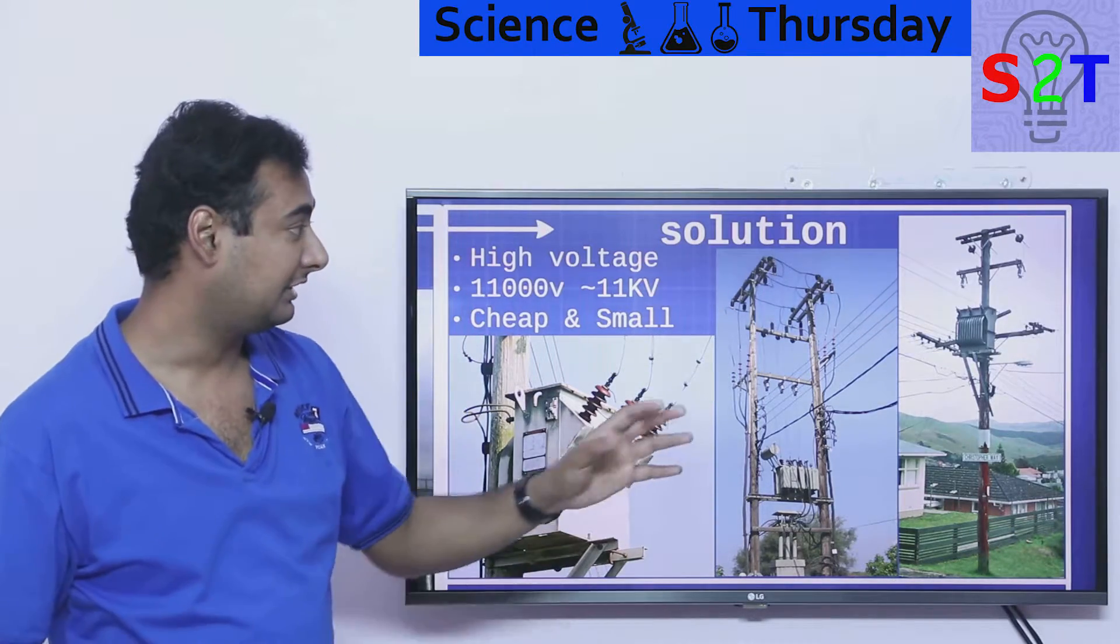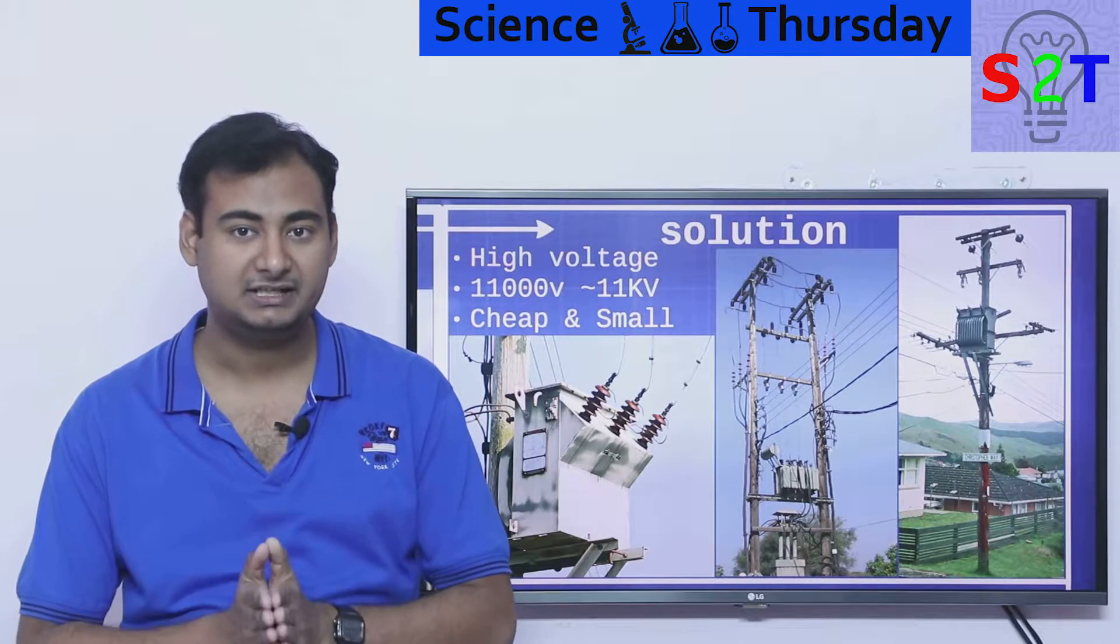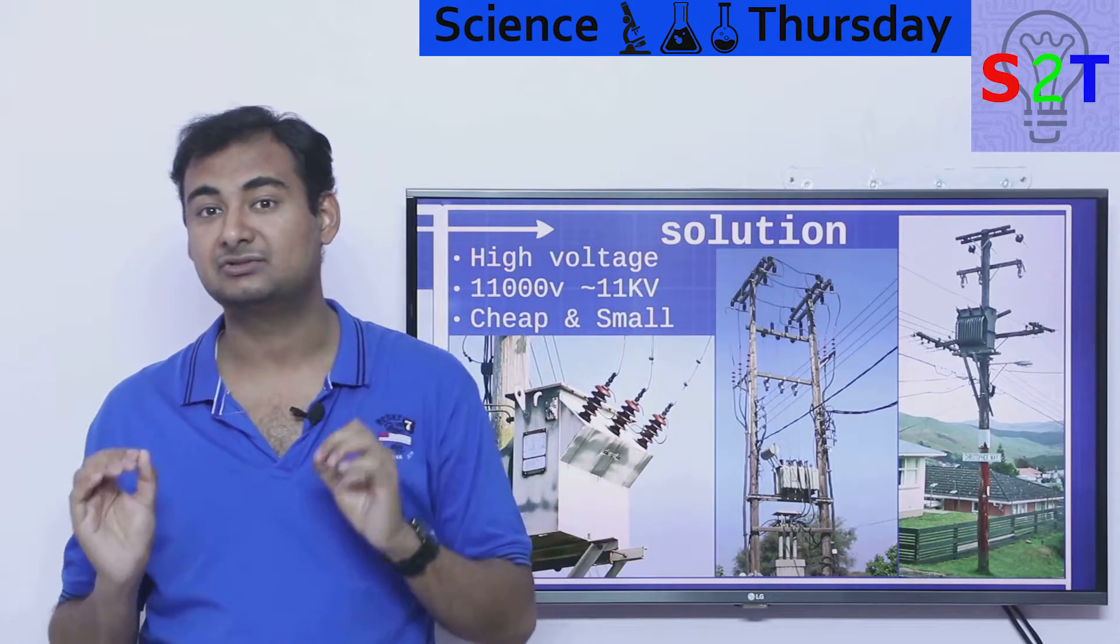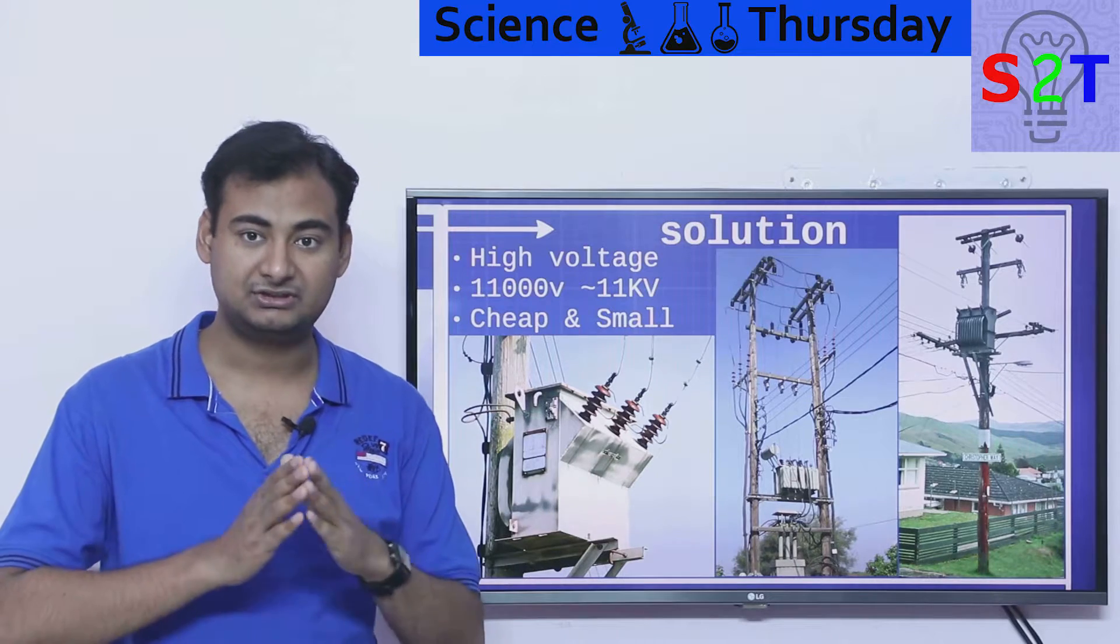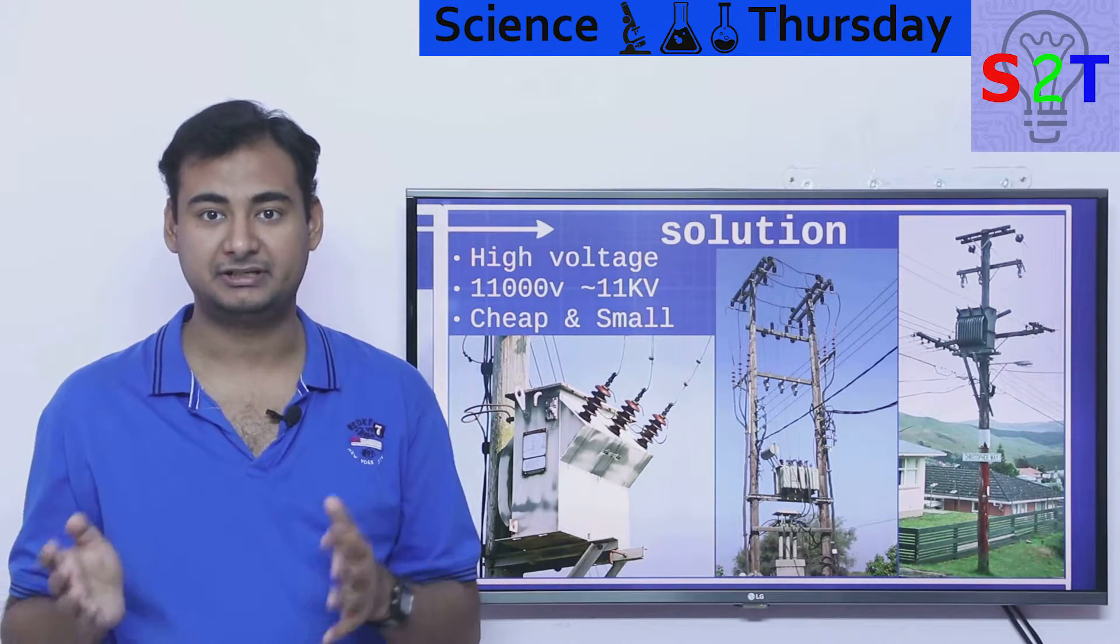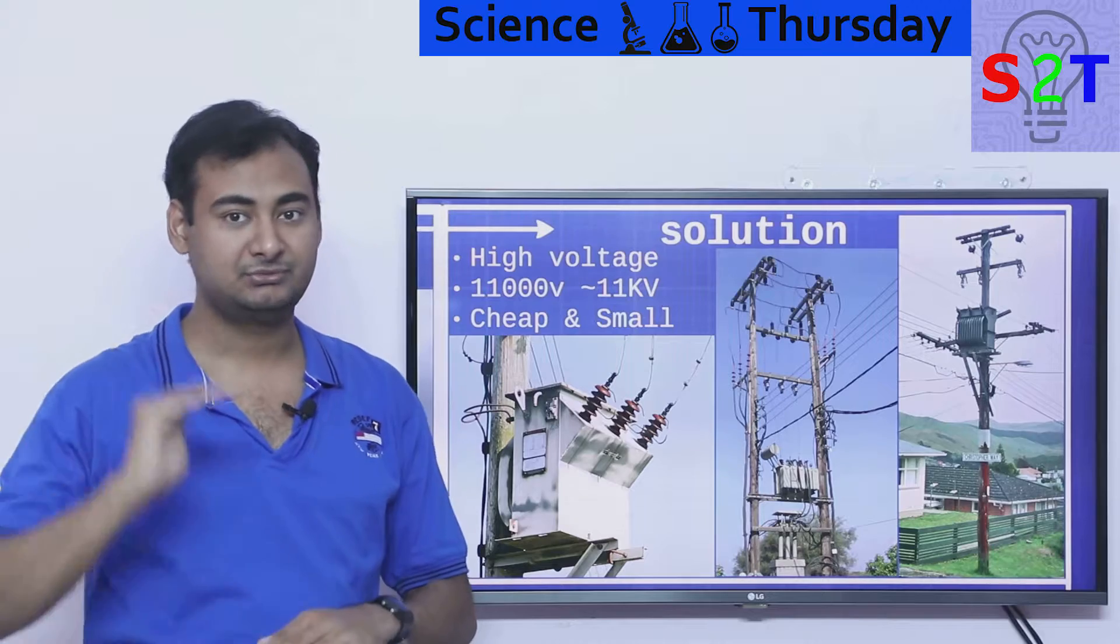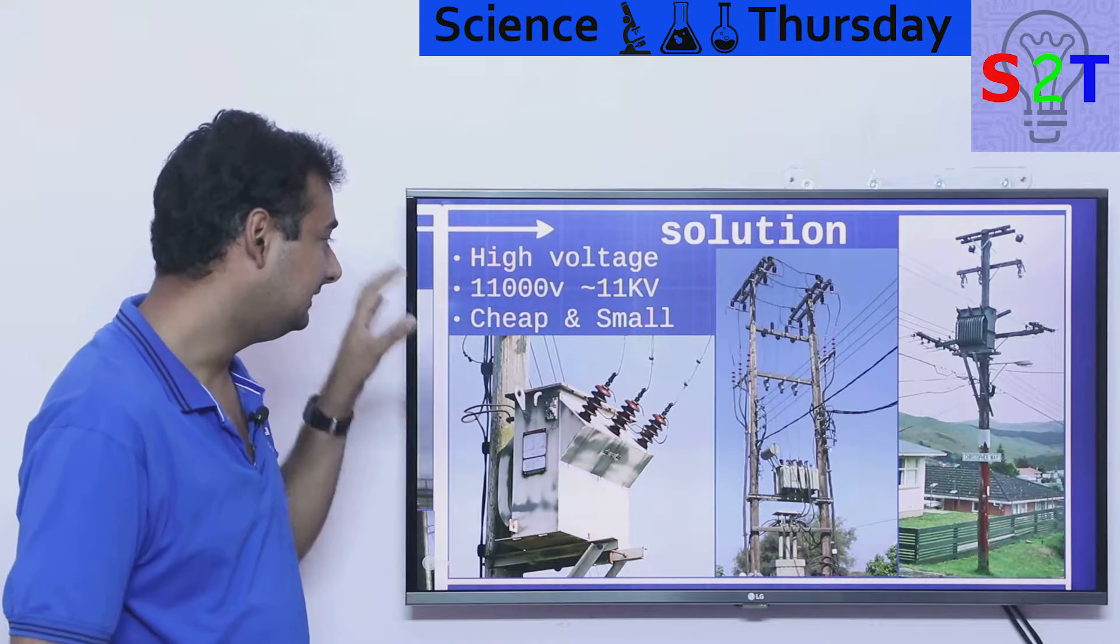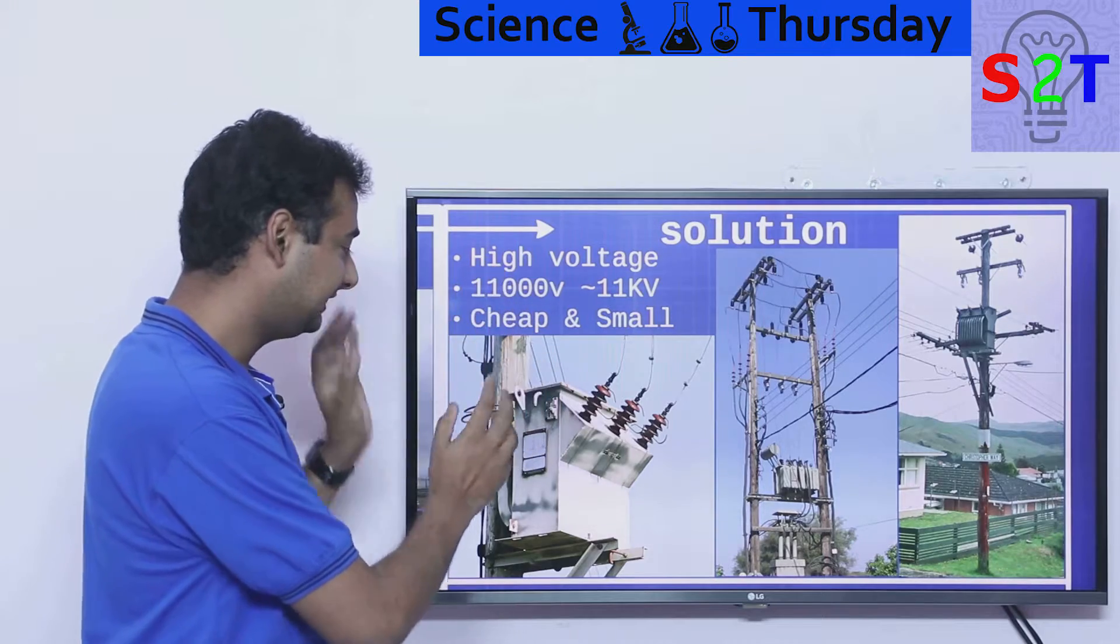That is infeasible for your neighborhood. For neighborhoods, 11 kV is a good compromise. The voltage is not so low that amperage would be too high, and it's safe enough as the air's dielectric strength - the air's ability to stop the electricity jumping from one point to another - is high enough. You also must take into consideration rain, because we cannot afford to put sheathing or insulation on these lines, it would be way too expensive. Is the voltage high enough to reduce amperage and manageable by air in a wet environment? Yes, then we settle on 11 kV.